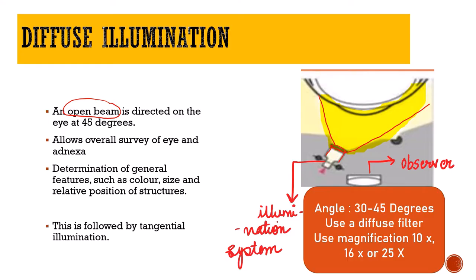Here the beam and the observer system are at a 45-degree angle. The filter used is a diffuse filter, and the magnification can be 10x, 16x, or 25x. The purpose of diffuse illumination is to allow an overall survey of the eye and the ocular adnexa. It helps determine general features such as the color of the eye, size, and relative position of structures. Diffuse illumination is usually followed by tangential illumination.